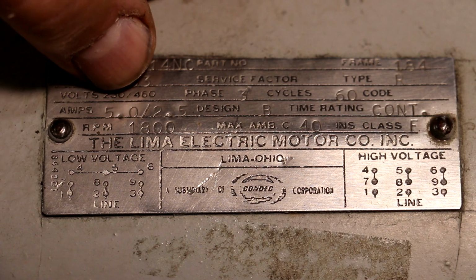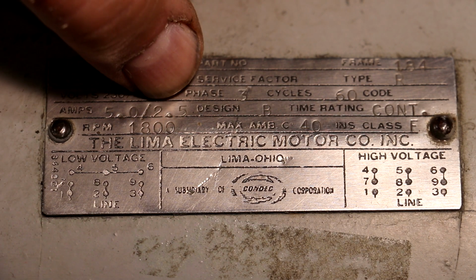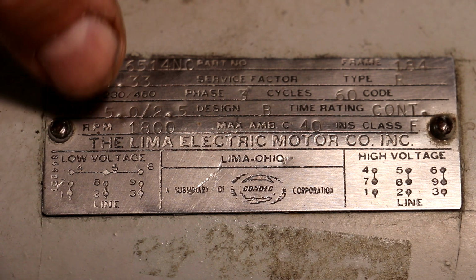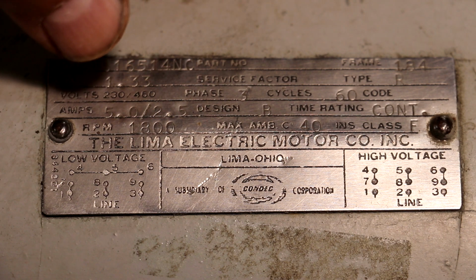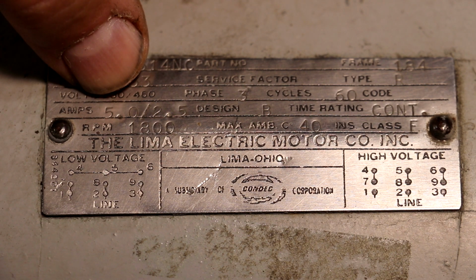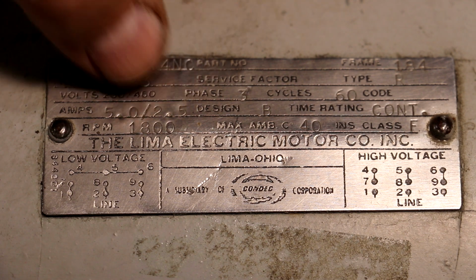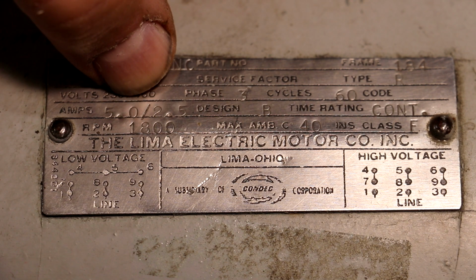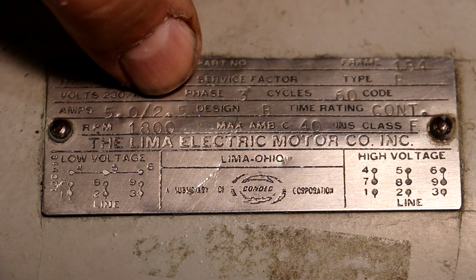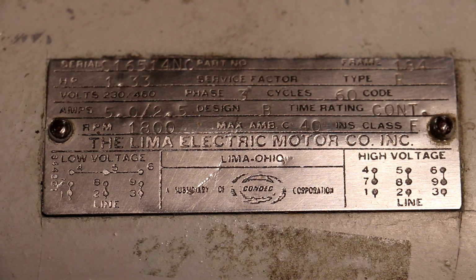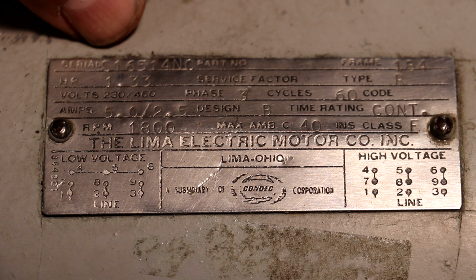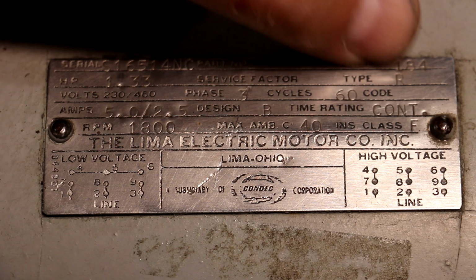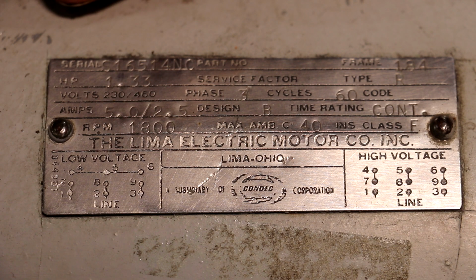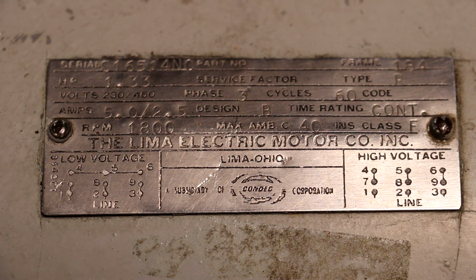Notice on here on the amps, it says 5 amps / 2.5 amps, and what that's saying is on the low voltage it pulls 5 amps, this motor does. On the high voltage it's only pulling 2.5 amps. So we will also need to change the heaters in the motor starter. I haven't even looked at that yet to have it for the correct amperage that this motor is going to pull, because right now if it's on the high voltage it's going to be on 2.5 amps, and I need probably different heaters in there to adjust for that. This is a 1.33 horsepower motor, 3-phase, 60 cycles, all that matches, 1800 RPM, but like I said, we need to change out the high-low voltage.